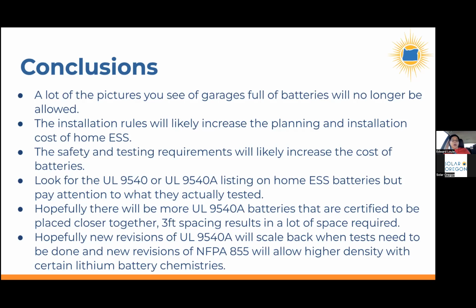But hopefully, those manufacturers will do these tests soon, and then we can install them stacked together in these different configurations. And hopefully, more of these battery manufacturers will test them in a configuration where they're placed closer than 3 feet apart, and then certify that it's approved to be placed up to, for example, 0 inches apart. Like SimpliPhi has certain batteries approved to have 0 clearance from each other, so you can butt them right next to each other. But that's just one manufacturer that has done the test. Many others have not.